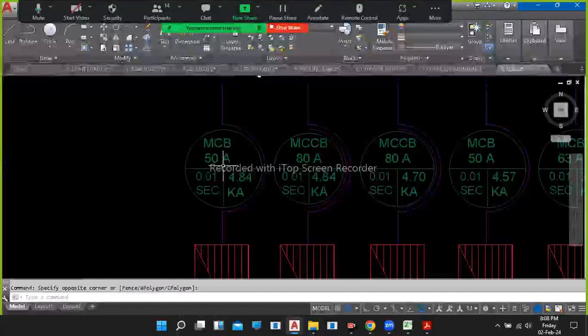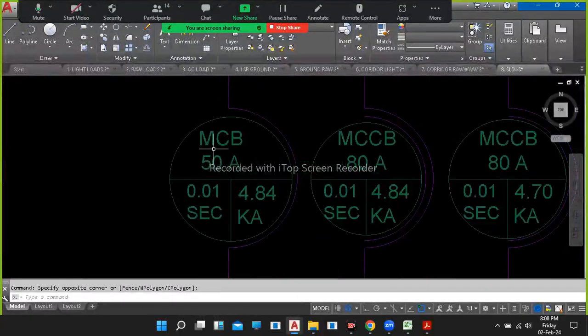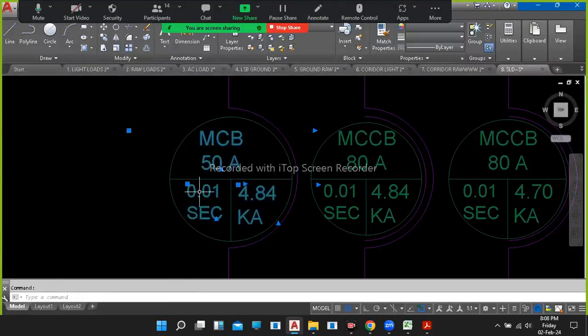Then for this, yesterday we calculated the circuit breaker. But here, he provided MCB, but generally we don't provide MCB. Okay, because as I told you, we'll be providing the circuit breaker, RCCB. We'll be providing RCCB. And this fault current and tripping time, we didn't calculate it. I'll tell you that later on, fault current and tripping time.